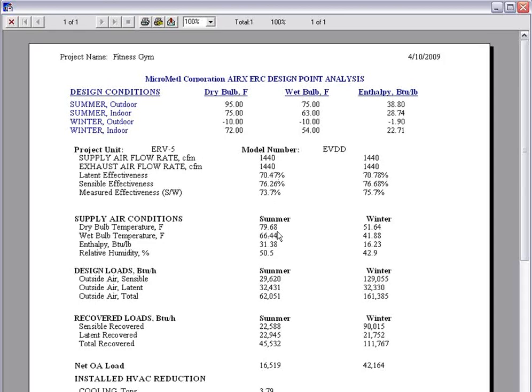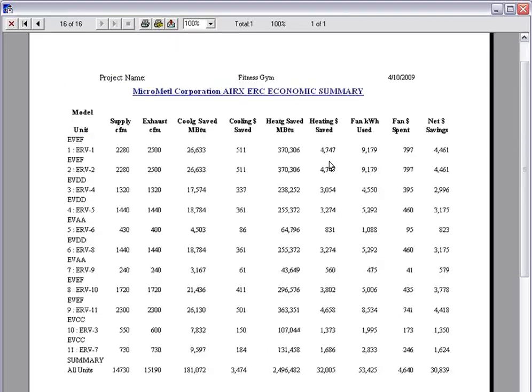So during the summer, we would go from 95 to 79 degrees with a specific wheel. In the winter, we go from -10 to 51 degrees. So that's the amount of recovery we get with this system. It would show us our design loads, and it would help establish recovered loads, how much we're actually recovering from that exhaust air. So this is efficiencies of the wheel itself, from that air exchange wheel.